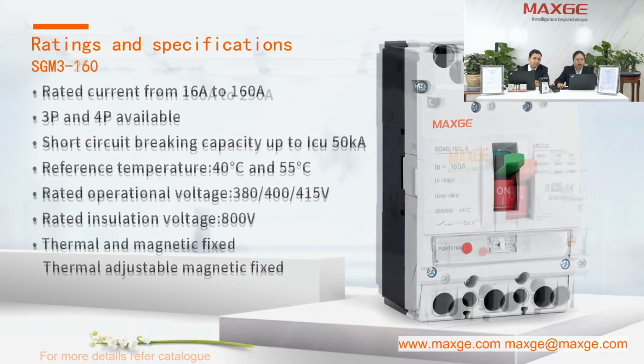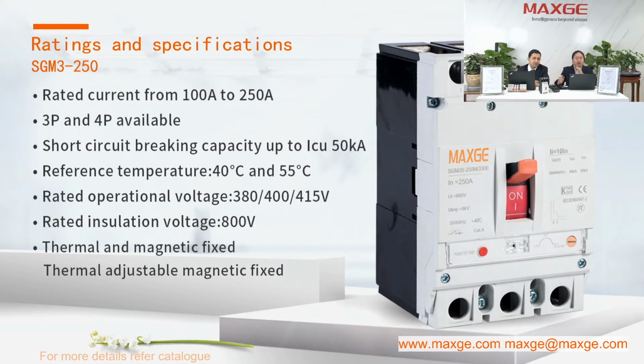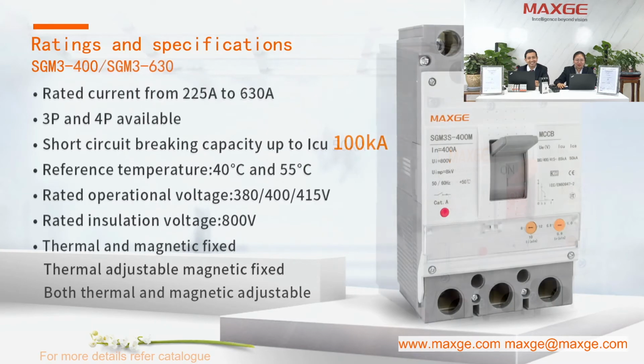Then the next frame is the 250 frame size. The rated current is from 100 ampere to 250, and we have 4-pole and 3-pole. Similar to the 160 frame, we have the thermal and magnetic fixed type, and the thermal adjustable but magnetic fixed type. The breaking capacity is the same, ICU 50K, divided into L type and M type. Next year we will have ICU 75K also. Oh, it is big.